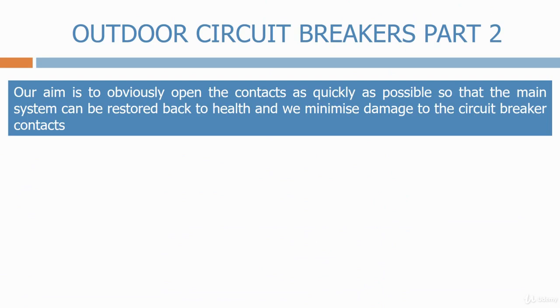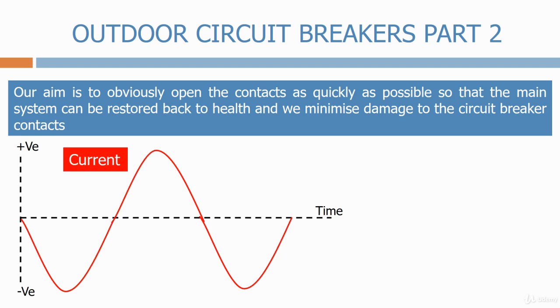Our aim is to obviously open the contact as quickly as possible, so that the main system can be restored back to health and we minimise damage to the circuit breaker contacts. Here's our current waveform from before. As we said previously, we have an opportunity at each current zero to break the arc. For a 50 Hz system, the current waveform crosses zero every 10 milliseconds. And for most circuit breakers, we aim to clear the fault within 30 milliseconds.